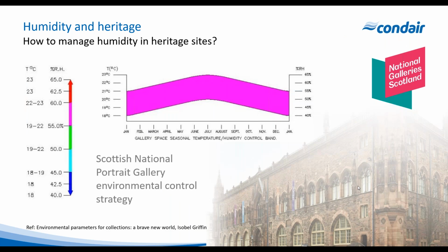And this is a really interesting study at the Scottish National Portrait Gallery, where they recognised that we could maintain the equilibrium relative humidity in the objects by sticking within that 40 to 60%. And in the winter, you can run the gallery at a lower temperature, but still remain in that safe zone. And that means that you reduce your heating and humidification costs because we have a lower set point.